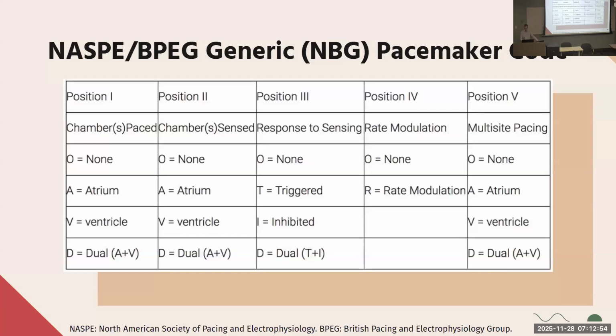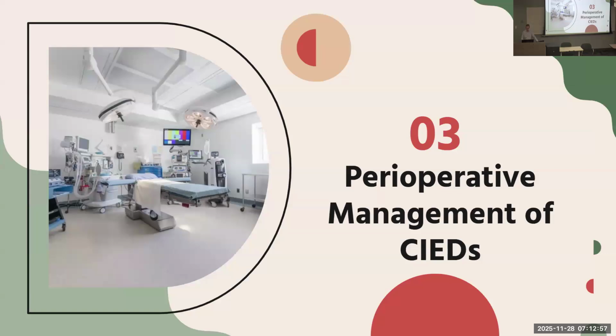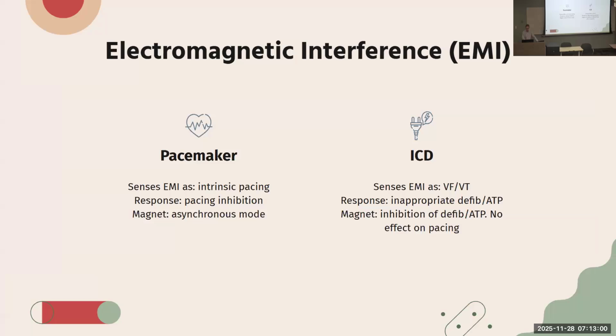I won't get into that here, but in terms of the perioperative management of pacemakers, the main concerns intraoperatively would be with electromagnetic interference, or EMI, and that is from inappropriately interpreting monopolar cautery. So for pacemakers, they sense the EMI as electrical activity in the heart, so they think the heart's pacing as it should be, and so the pacemaker will inhibit its pacing. It'll inhibit itself. And so that can result in significant bradycardia or an arrest.